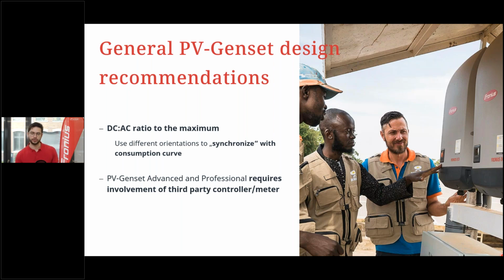The inverter will not produce more than 100 kW, but the 150 wouldn't occur anyway at every time of the day, so why not push it to the maximum? There is no warranty loss or whatsoever. And also, you might want to consider an east-west installation to really synchronize the load to the production. Because on the east-west installation, you have earlier in the day and later in the day a higher production, which can be curtailed even better for your load profile.